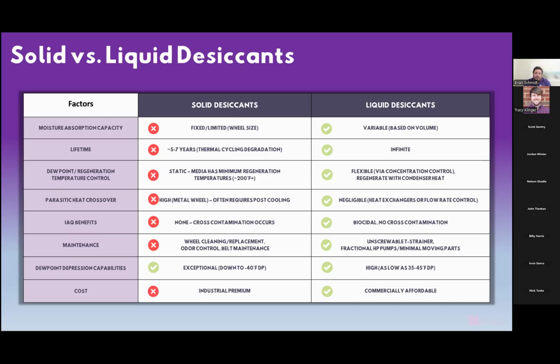Some of the IAQ benefits, again, because this is a very salty solution, it is biocidal. There's no cross-contamination. Maintenance-wise, you'll see at the very end of this presentation what the maintenance of these systems is, and it is extremely minimal. As I mentioned before, you never need to top these systems off. The liquid desiccant doesn't leave the system itself. We do have a little T-strainer that you should check out every time you change the filter, but I'll show you that here in a little bit.